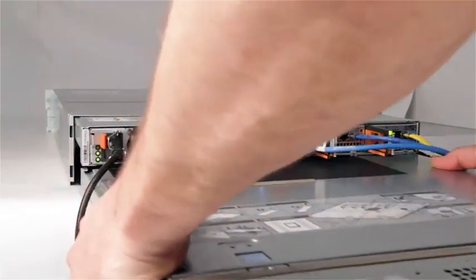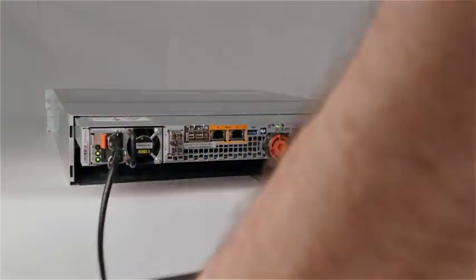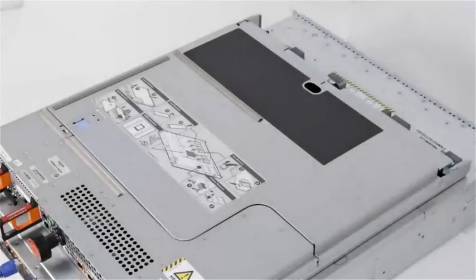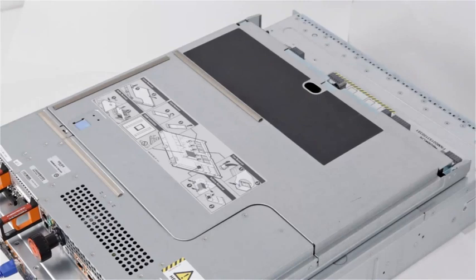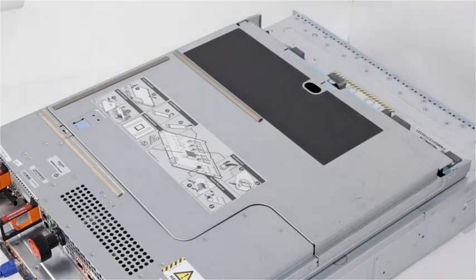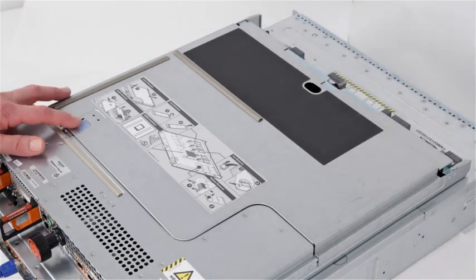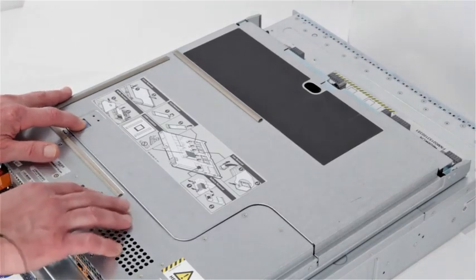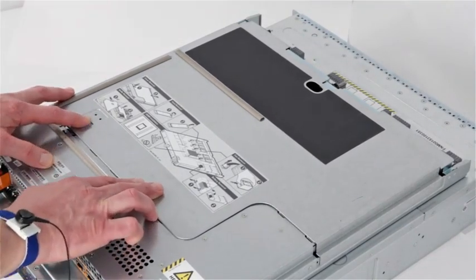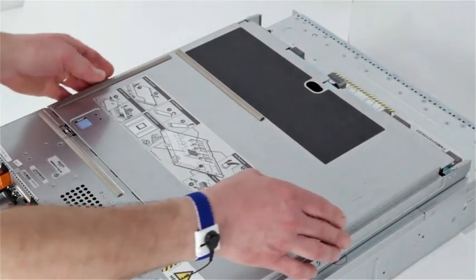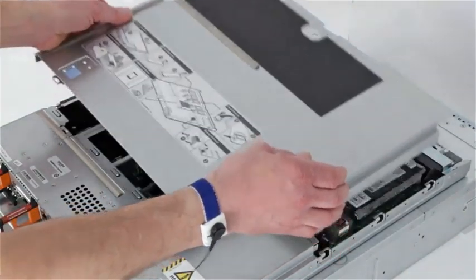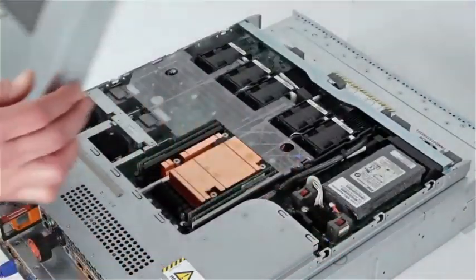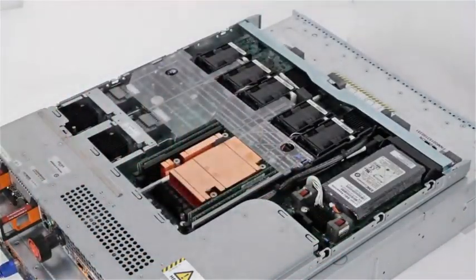Place the SP assembly with top side upward on a clean, flat, static-free work surface. Verify that all SP assembly LEDs are off to ensure that the SP has completed its power off after the removal from the DPE or disk processor enclosure. While pushing down the blue release button, slide the top cover rearward approximately one-half inch until it stops. Lift the top cover upward and remove it from the SP.